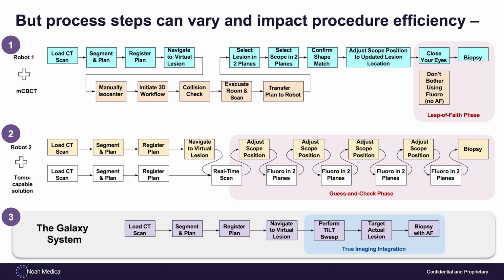So for example, with any other robot using a mobile cone beam, you're doing the normal aspects of uploading a CT and driving your camera out to the lesion, but then you have to stop, bring in your mobile cone beam, use a manual isocenter, do the 3D workflow, make sure there's a collision check, and get out of the room. I hope you're getting out of the room if you're using it. Put that information into the robot, and then update your lesion and look for where that lesion is in the new image and where you are in relation to the plane of that image. So it does change how you approach each patient and the amount of time you have.